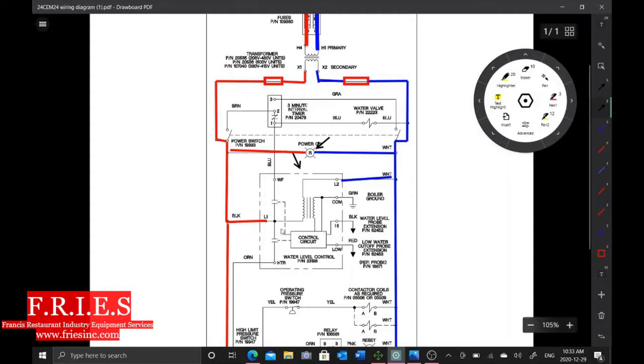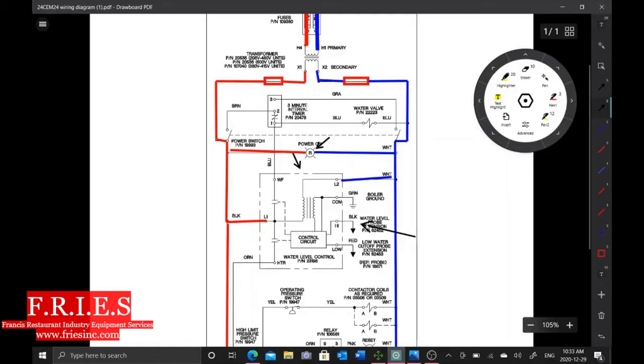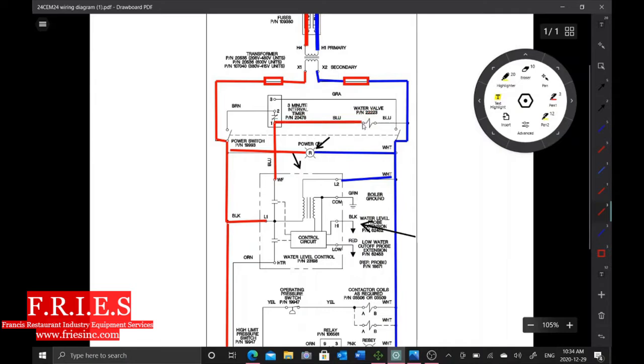And as soon as this board gets power and the high water level probe is not grounded right here, we're going to send power to our solenoid. So this WF terminal is going to send power up through our five-minute timer. It's going to send the L1 side to the water valve.